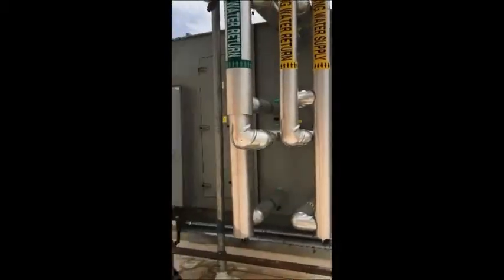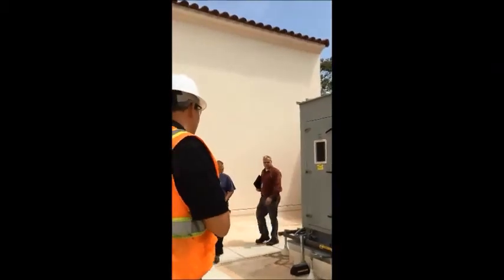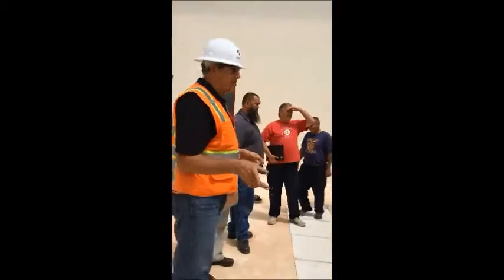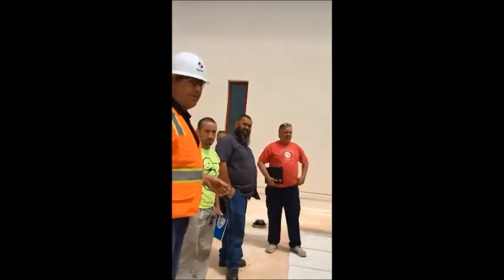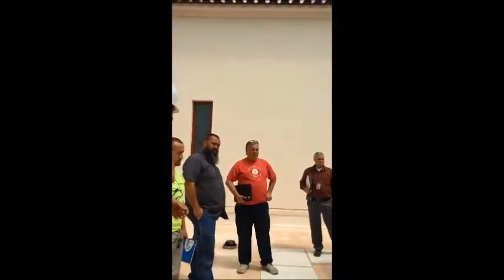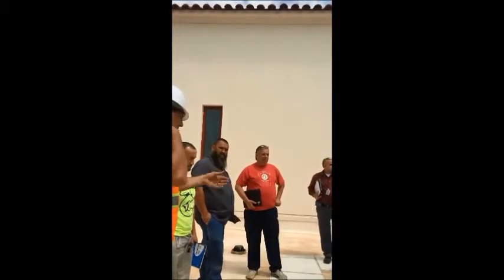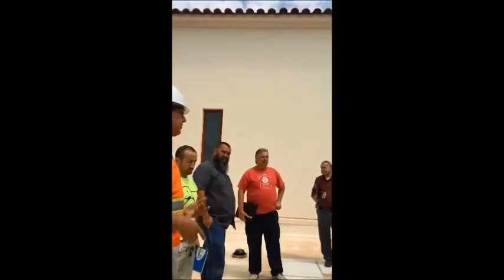So here on 3 is a VAV unit, 2 VFDs, 1 supply, 1 return. Right now it's at 100% set. That's why you're feeling the exhaust come out the end, because it's taking the return fan and blowing all the outside air that's going in the building, bringing it back outside for this building flush.